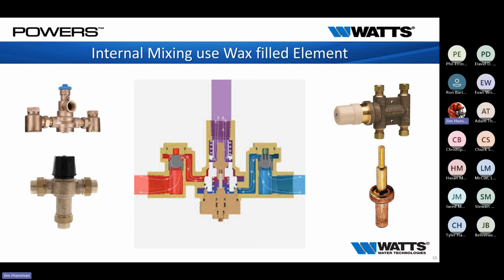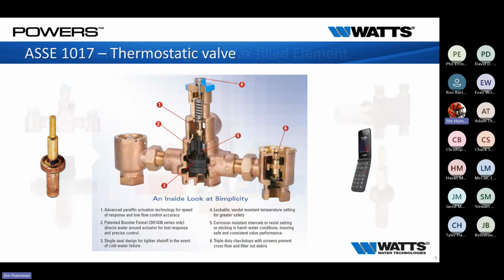Here's some of the issues we run into with these thermostatic valves. If you've been in this trade for years, you'll find out quickly that every manufacturer, and I'll talk about Powers since that's who I'm with, but 99.9% of manufacturers will tell you this valve needs to be completely rebuilt at minimum once a year. The reason is water quality.